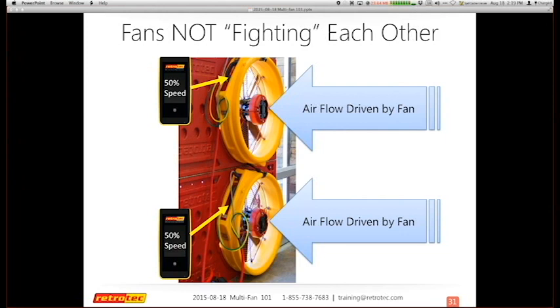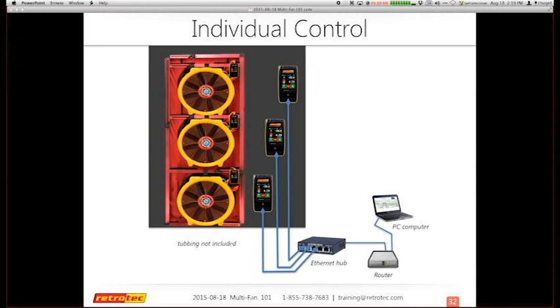Let's go through the same scenario where I have my connections back to the computer, but a common flaw people make is they connect their gauges as they normally might for a single fan, and realize this is a major challenge. The fans will begin to move, all rotating the same way, but then suddenly some of them will slow down, and some will begin to go in reverse. Depending on how many fans you have or how far away they are, if they're not right in your visual, this may be a challenge for you.